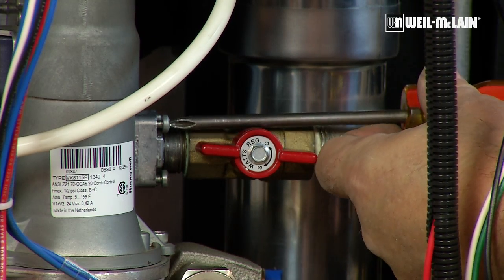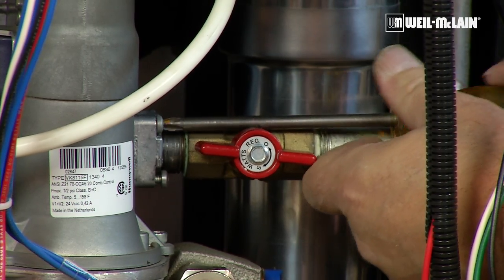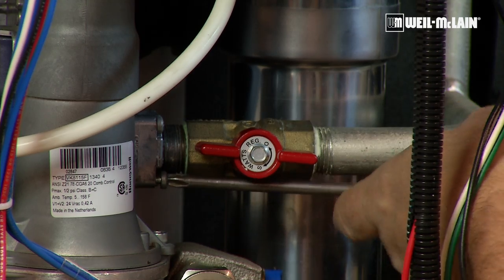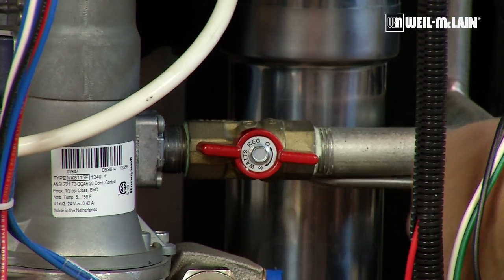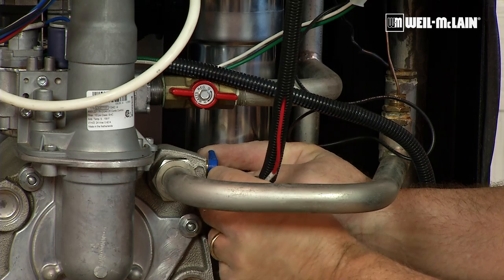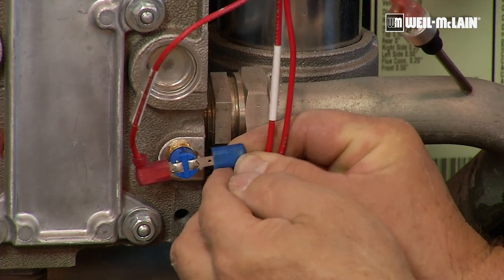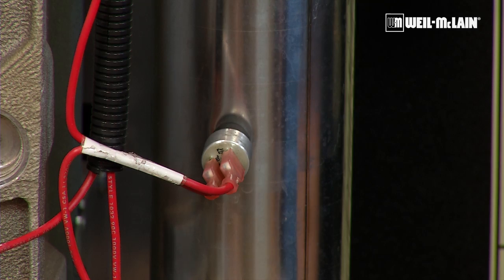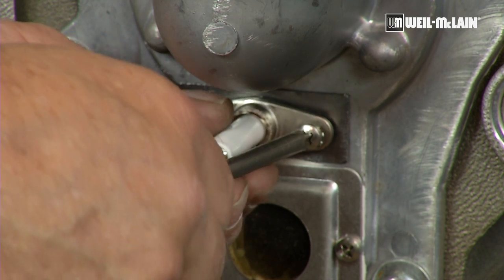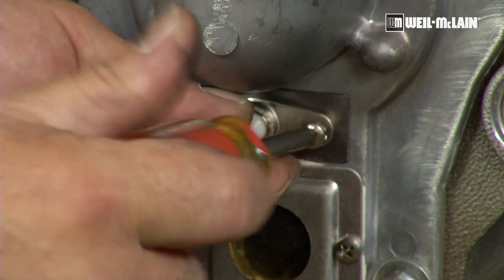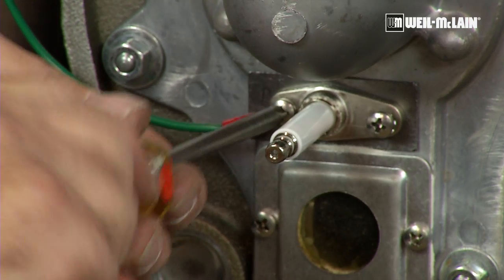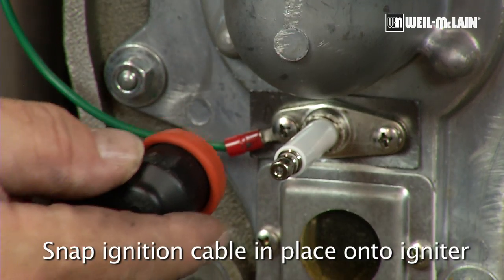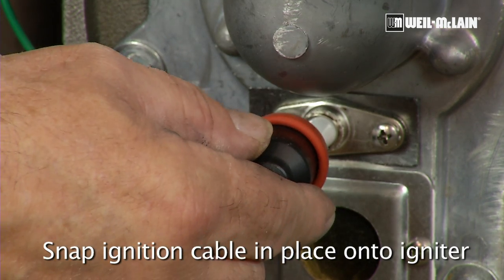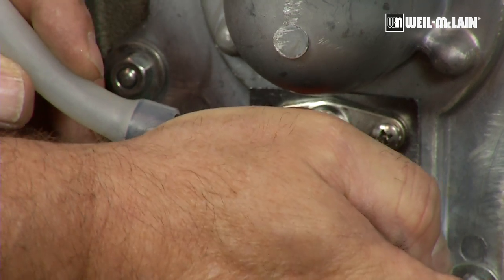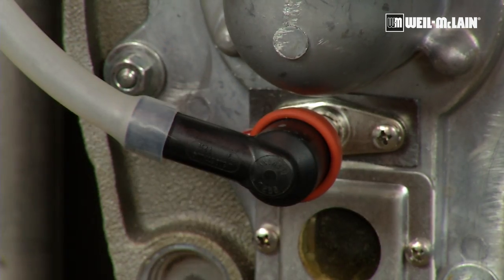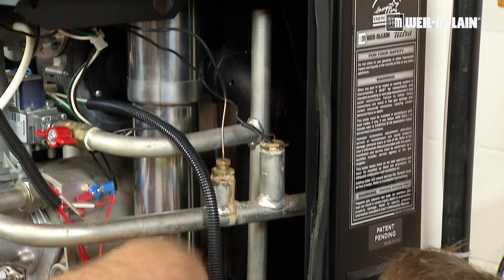So when we're reattaching the gas manifold to the gas valve, you need to leave your screws loose initially until all 4 screws are in the adapter block. Otherwise, you have a hard time locating the connection point. After that step is completed, we're going to reattach the wires to the specific components here. Okay, and the last step here is going to be the installation of the new igniter. We want to make sure that we attach the ground wire to the flame sensor. Snap to it, make sure we have a positive lock on there. Now the last piece to be installed is the air silencer.